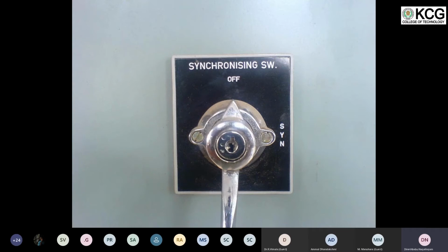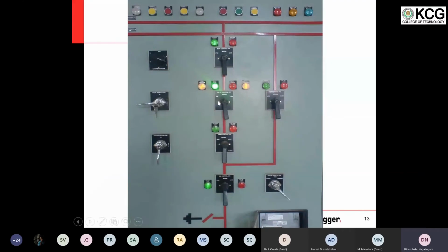Let us assume a breaker is lying between a bus bar and a transmission line, like this. Okay, this breaker is between a bus bar and a transmission line. From here, this is a line. Now there are 4 conditions. One is both sides are dead, that is, no voltage available on both sides. Second condition, live bus, dead line. Third condition, dead bus, live line. Fourth condition, live bus, live line. So there are 4 conditions in a real-time scenario.